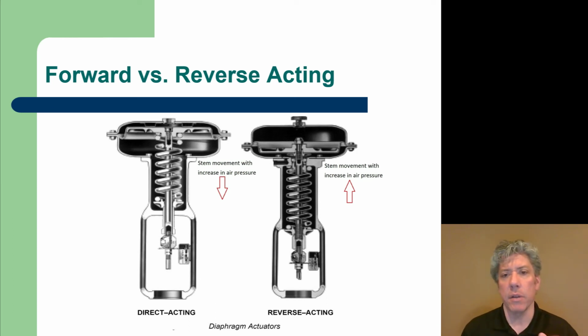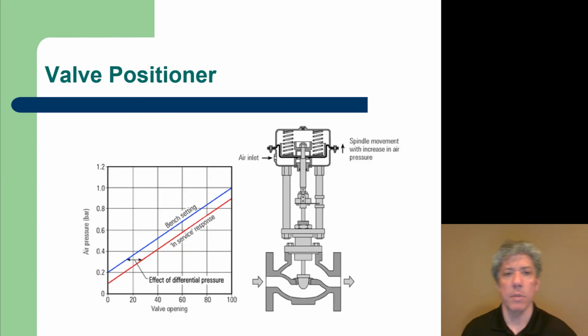Reverse acting, on the other hand, on the right-hand side, you'll notice that the air inlet has been plugged at the very top of the valve. Rather, pressure is introduced on the underside of the diaphragm, and you'll notice that the spring is in an opposite configuration, where now the top of the spring in this right-hand diagram is grounded to the yoke or the frame of this actuator, and the bottom end of the spring moves up and down. Now the air comes in, the connection is a little difficult to see, but if you look on the left-hand side of that right diagram, you'll see a small black area that's sort of like an L shape. That's where the air would come in under the diaphragm in order to modulate the diaphragm position.